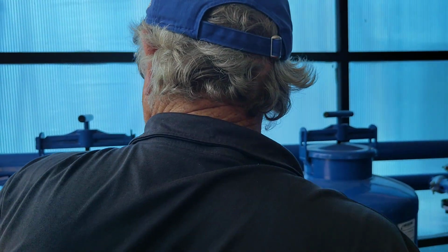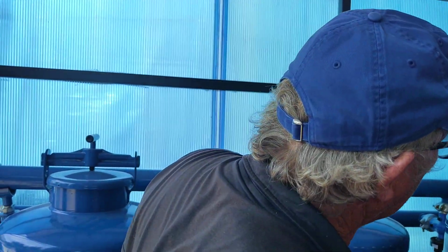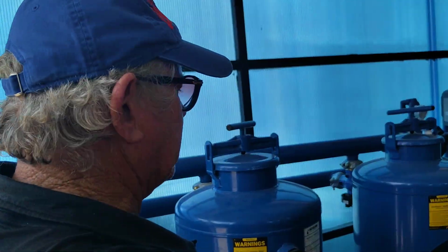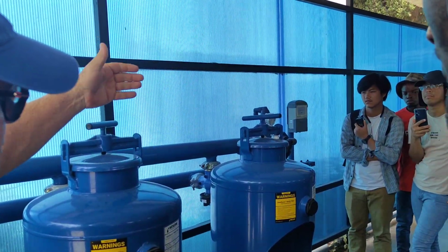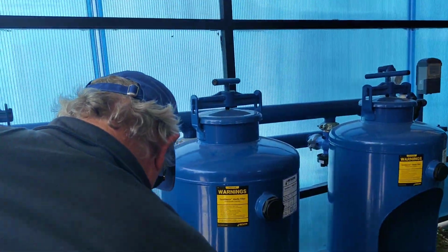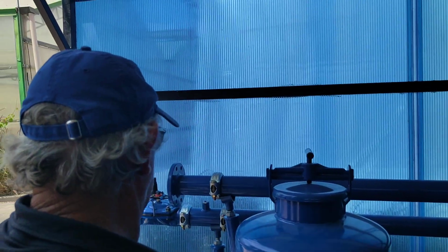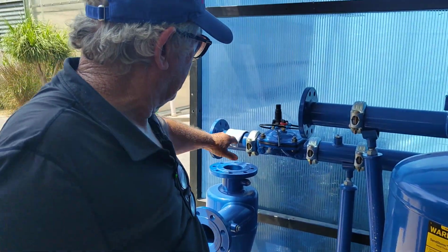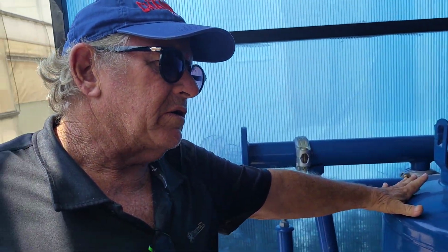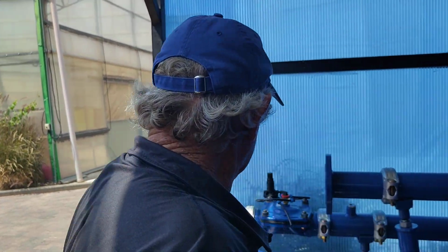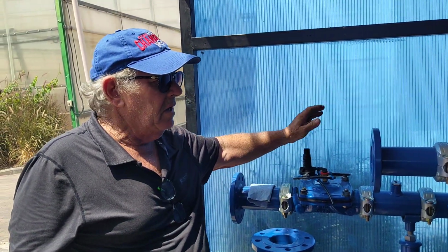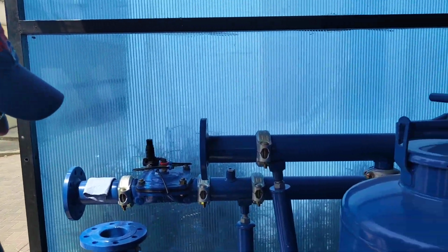In between, we have a few things that I want you to know about. First, the air valve over there. Since the pumps bring water with air, we have to release the air, and that's what these valves are doing. So it's mandatory to have an air valve in the system. Second, we have here a valve with pilot. I will explain over there, but this valve with pilot regulates the pressure, so we can control the pressure which is coming in. And of course we can close and open it as a normal valve, but the reason that the pilot is right here means that we control the pressure perfectly.